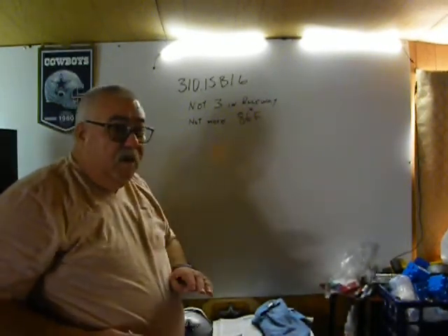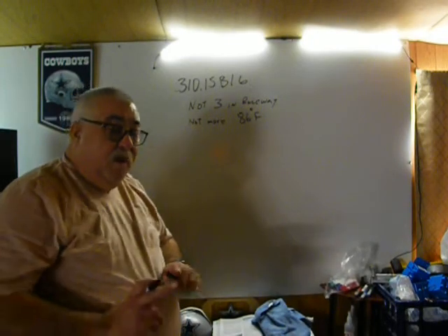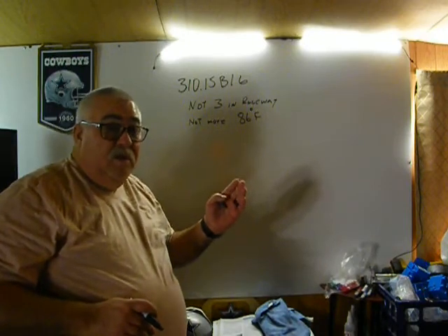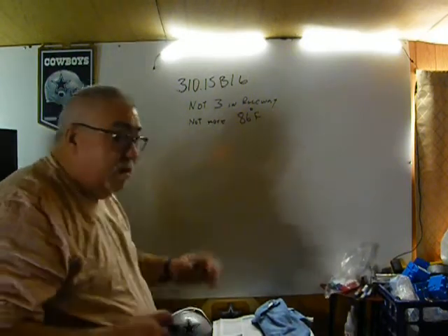If it's less than 78 degrees because it's colder, okay, we can add more amps on it. If it is hotter than 86 degrees, well, we can put less amps on it. So we have to derate the wire.